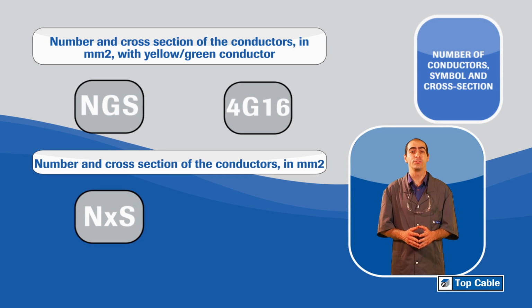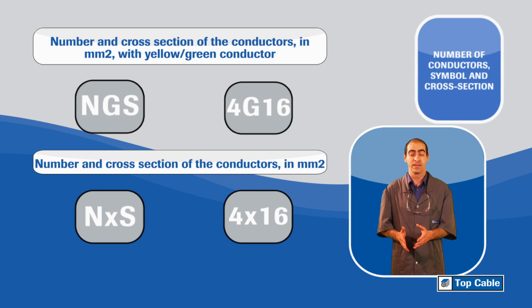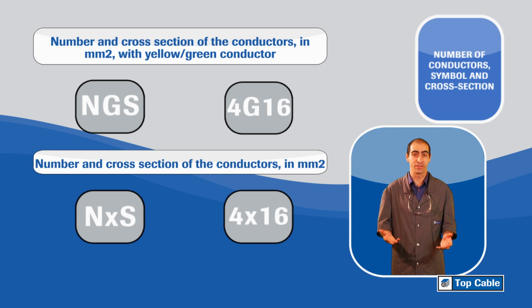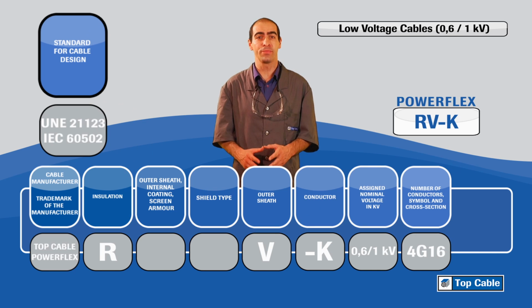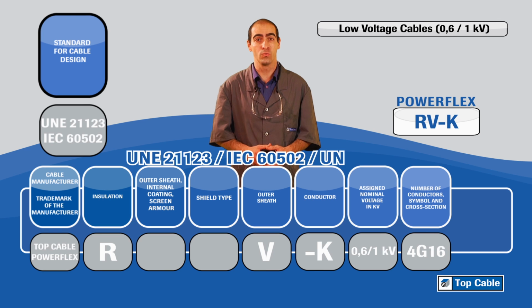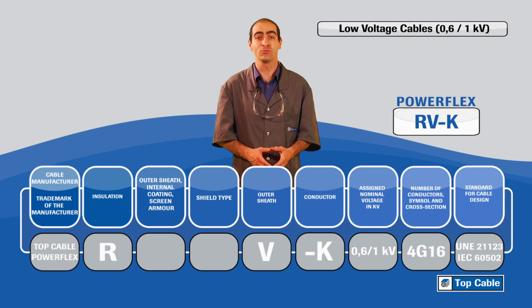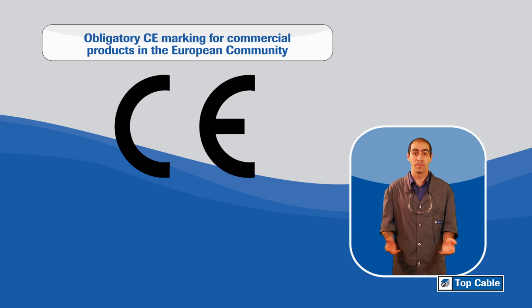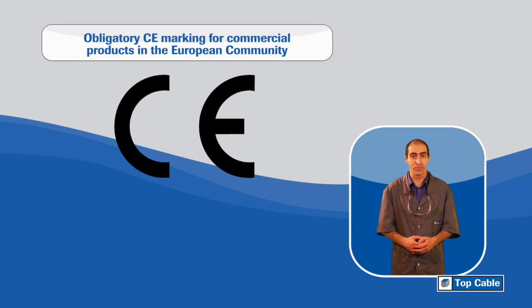NxS, number and cross-section of the conductors in millimeters squared. In this example, 4x16 means 4 conductors of 16mm squared. The references to the standards for the design of the cable in question are indicated last. UNE 21123, IEC 60502, UNE 21150. Additionally, the markings of the cable can contain additional details, like CE, obligatory CE marking for commercial products in the European community. The mark can be on the product or in the packing.